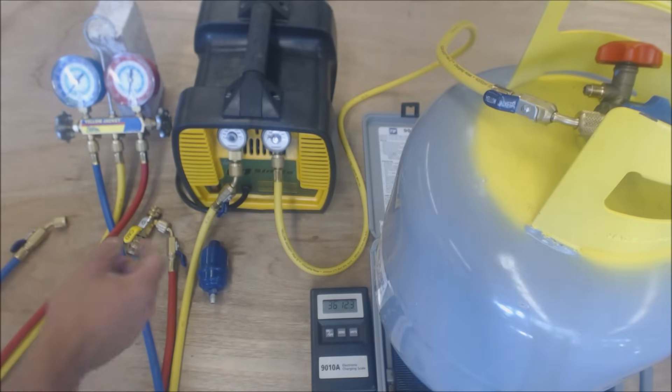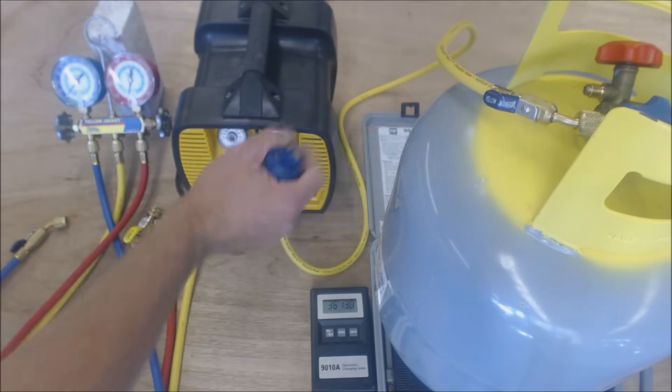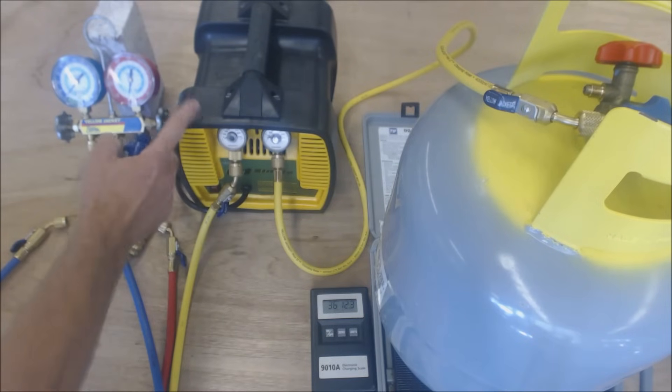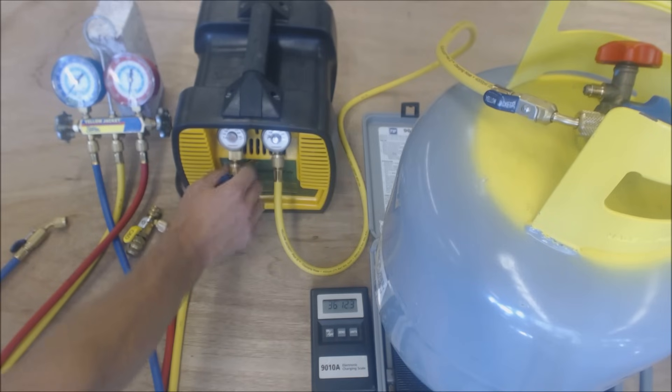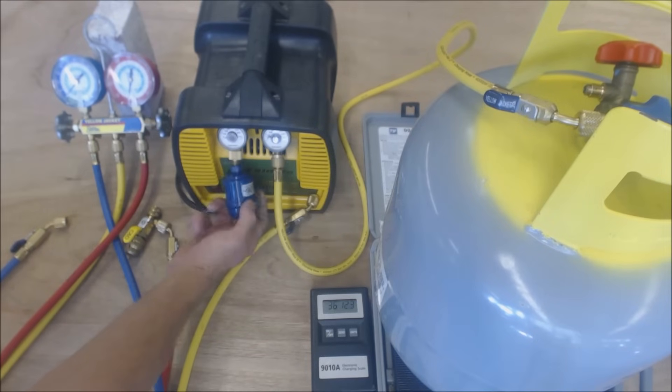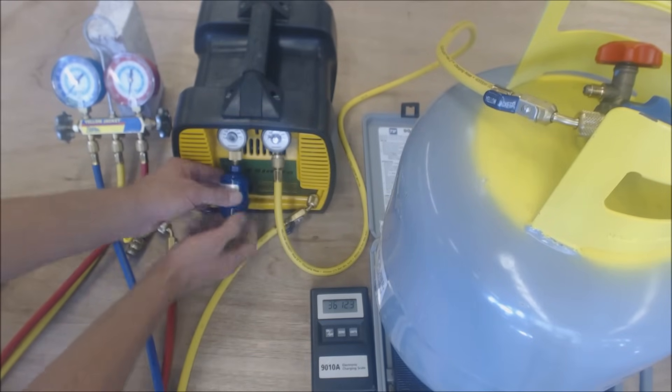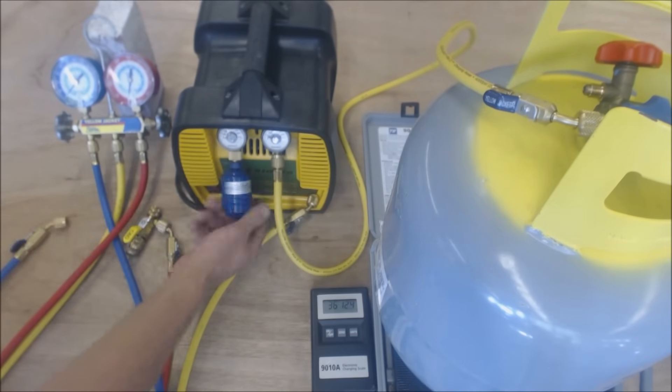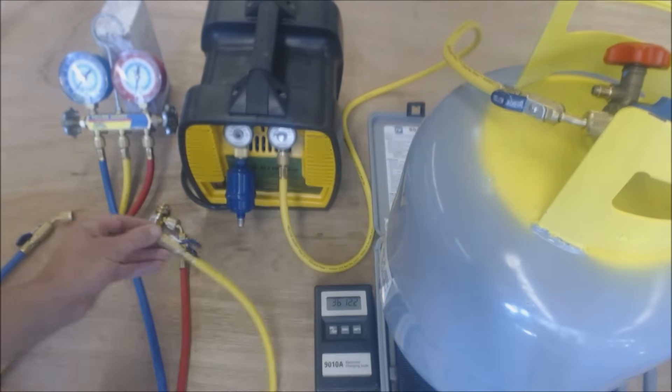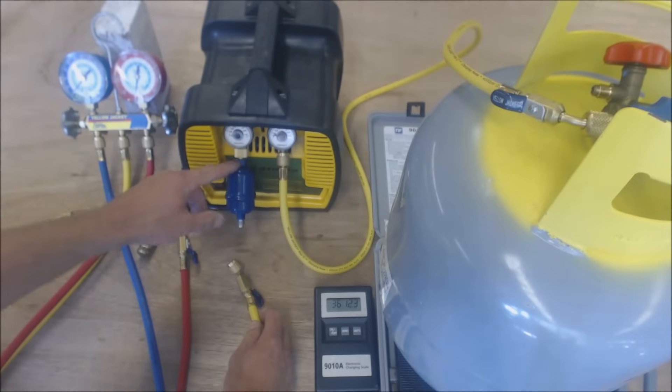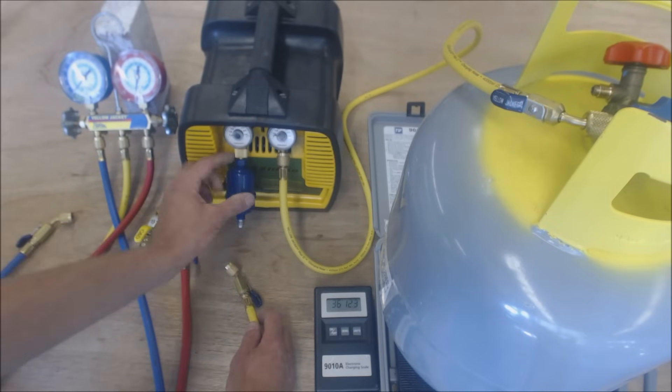Another thing is if you were planning on reusing this refrigerant in the bottle and you want to keep your recovery unit clean, you can actually go ahead and put a filter dryer in place right here. Put your filter dryer in place. If this is just a flare section right here, you're going to want to put a little bit of refrigerant oil in there beforehand—the refrigerant oil that you're dealing with.